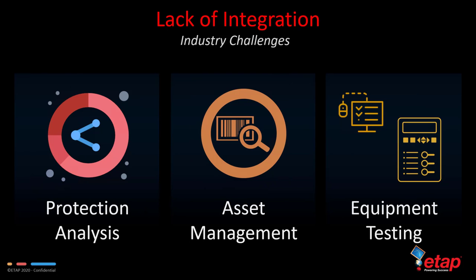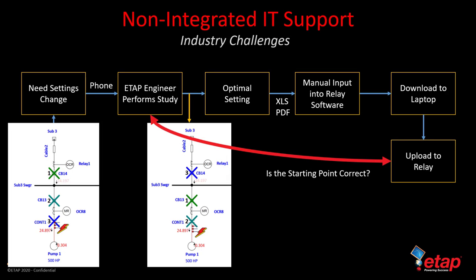Another industry challenge is lack of integration. Typically when we do our protection analysis, we produce a settings report, but the settings report is not the same as a setting file. So there's time spent in converting the settings report into a setting file that can be essentially uploaded to the relay. And this is essentially prone to errors, it's time consuming, and requires double data entry. Further, the legacy systems, especially the asset inventory databases, are not well integrated with any other central asset management system. So therefore, there's a need to link the inventory with the required components that you determine as a result of the study. And finally, equipment testing is also handled as a separate silo and not integrated with a centralized database management system.